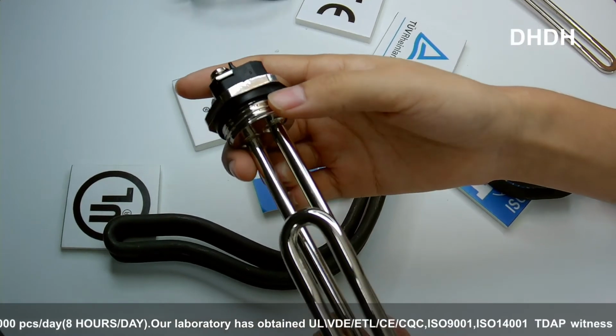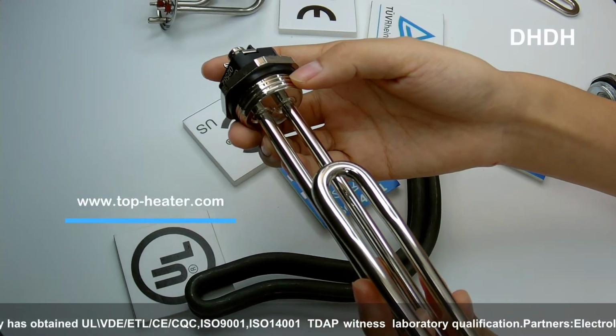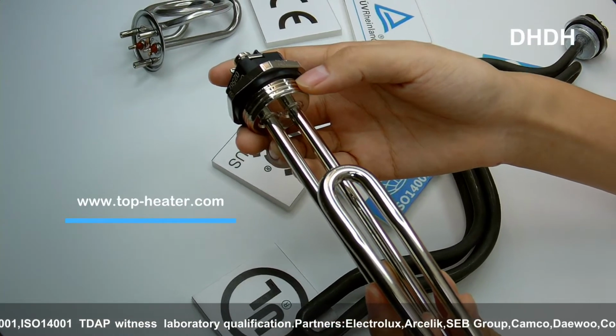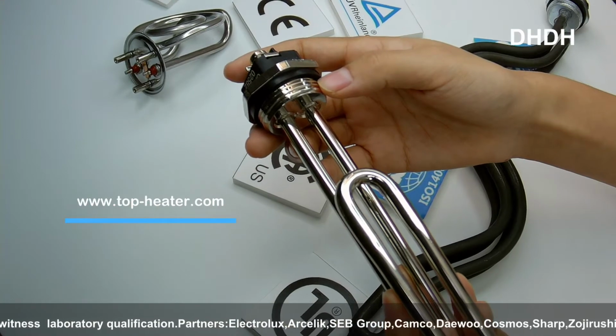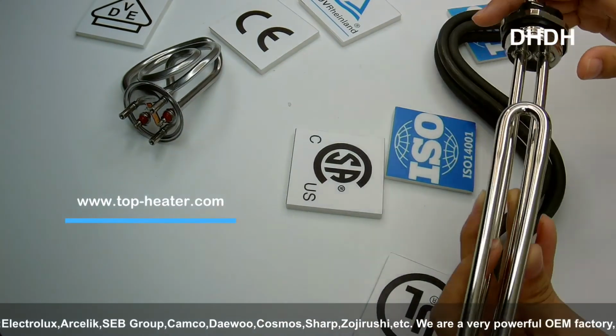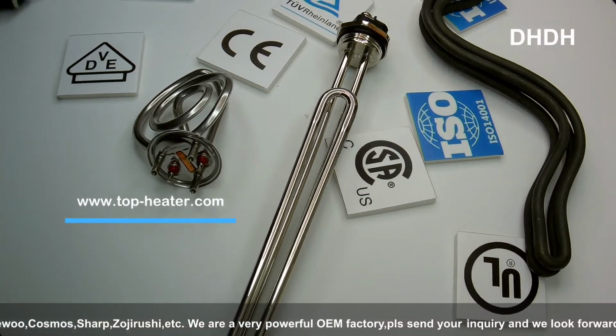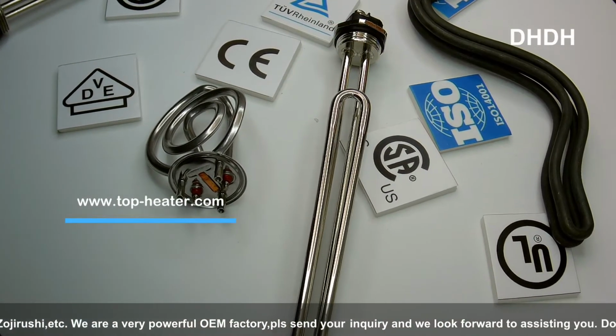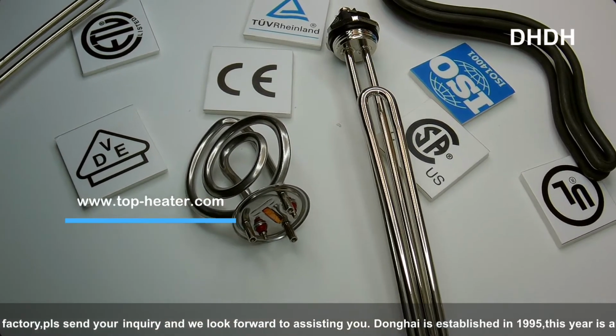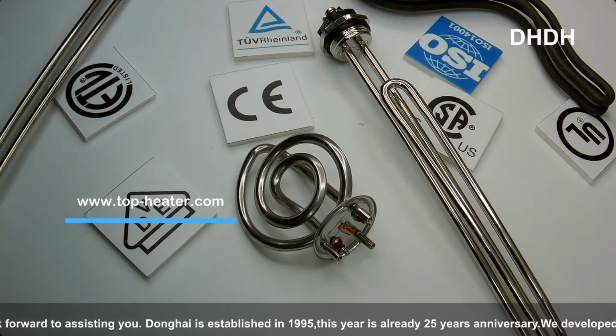So it's dangerous. If the silicone carbonizes, the tube can burst in some cases. So we press the bending area and make the MGO tight again so it can work normally. On the other hand, after bending, there will be wrinkles on the bending area. After pressing, it looks nice. With such pressing technology, the tubes work without danger from the silicone oil, and the surface also looks nice.